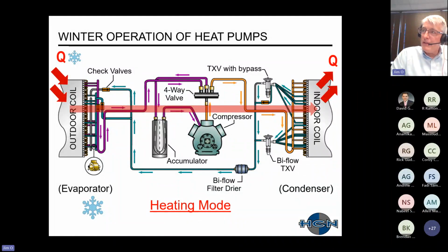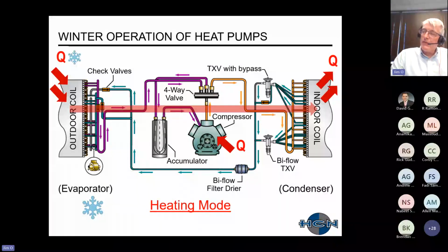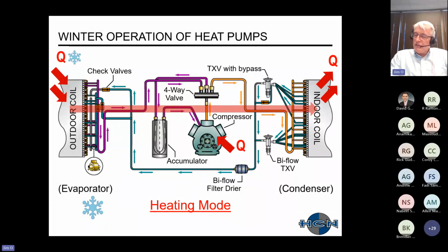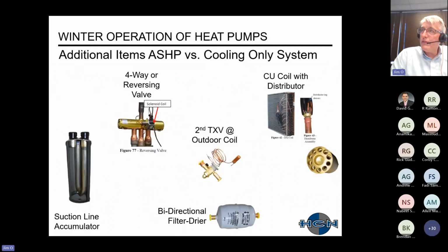And then the other benefit in the heating mode with heat pumps is that you have a compressor. That compressor's inefficiency is essentially adding energy/heat to our refrigeration system, and therefore that energy also gets expelled to the space.